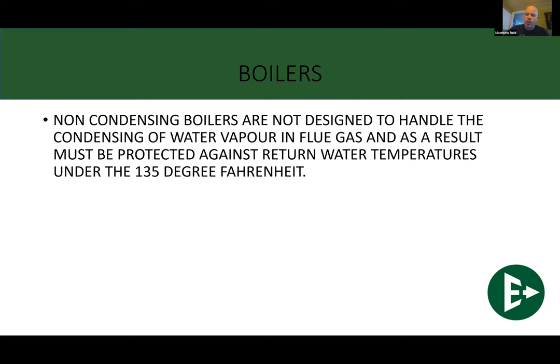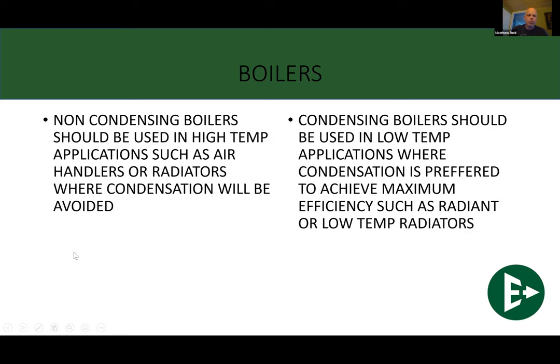Much more commonly, we see 180 degrees being supplied with a non-condensing boiler, to make sure that with regards to the delta T that we give to the system, we're well within that usual industry standard of 20 degrees that can push us way over that 140 mark. So that's what we need to see with a non-condensing system.